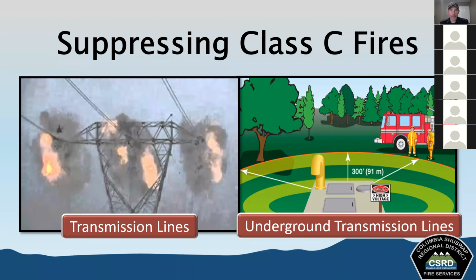So we need to cordon off a circle with a radius equal to the distance between power poles around the point where the power line contacts the earth. Basically the span of the power poles, that's how big of an exclusion zone we need to have. If a ground fire starts, we wait for the fire to burn away from the point of contact before we attempt to extinguish it, okay? For maximum safety, only utility personnel should ever cut these kinds of electrical power lines, right?